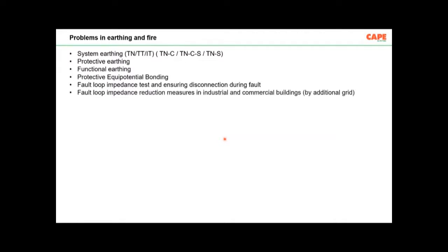Protective earthing, like connecting the steel pipe, firefighting pipe, to your equipotential bonding conductor in a high-rise building: mostly it's missing. People don't do this. Functional earthing means that for the operation of electronic equipment, you are supposed to connect it as I said in one of the slides. Instead, what we do is take a wire and connect the equipment to an earth pit in soil. This is wrong. Protective equipotential bonding mostly is a problem. Fault loop impedance test and ensuring disconnection during fault is also very rarely done.